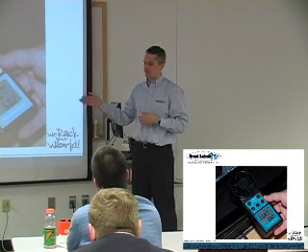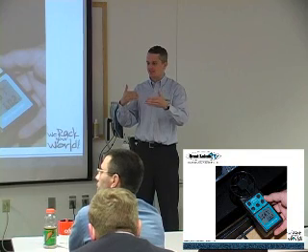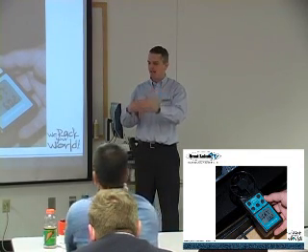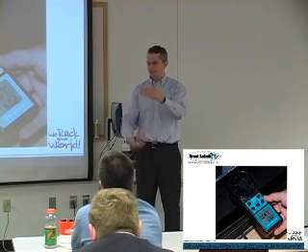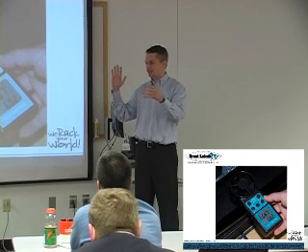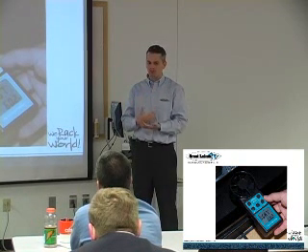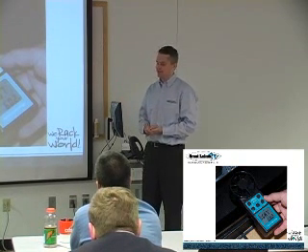One of the reasons that the diverter works well is because of that resistance that you meet between the mesh and the front of your enclosure equipment. It does not allow the air to go out. But the reason that we still use mesh as opposed to a plexi is redundancy.